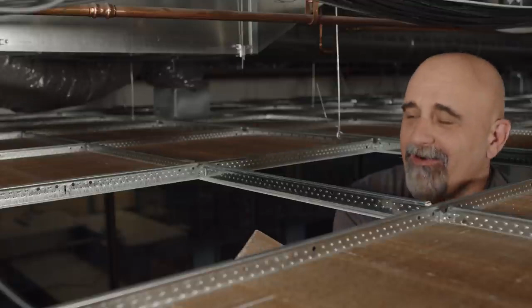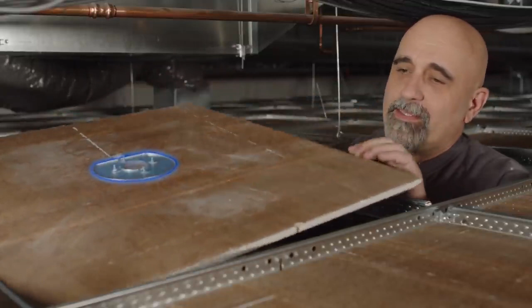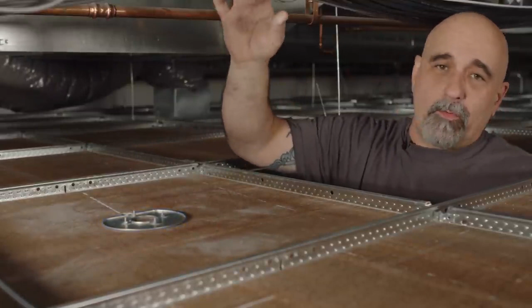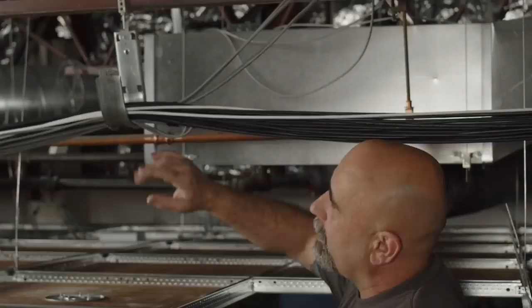All right, so we're up above the grid. I set this tile with the AP mount for it already so we could have that in place. And I thought I'd point out, remember I talked about keeping the cable supported and on your own support. We use J-hooks, supported with beam clamps right to the building structure. These all run back down towards the MDF, and then everything continues on down to all of the other field locations. Keeps it nice and tidy. We're not supporting off of any of the HVAC, the duct work, or anything else.